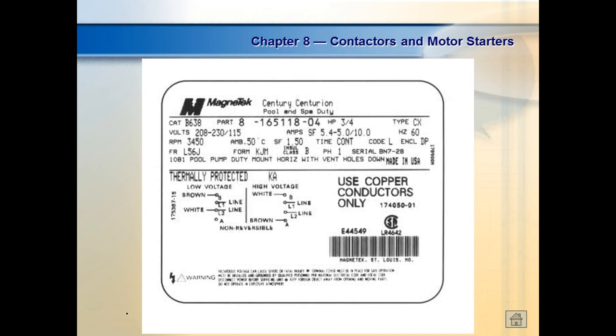Because it's going to try to produce what? 3/4 horsepower at a lower voltage. Well, that's why it requires more current to get 3/4 horsepower out of what? Out of 208 volts than it does what? At 230 volts. So we're going to run ours at 208. That's what we have over there. Y'all measure around 209 or something like that, right? So let's say we're going to run this motor on our power supply. Then what I'm going to use is I'm going to use the 5.4 amps.